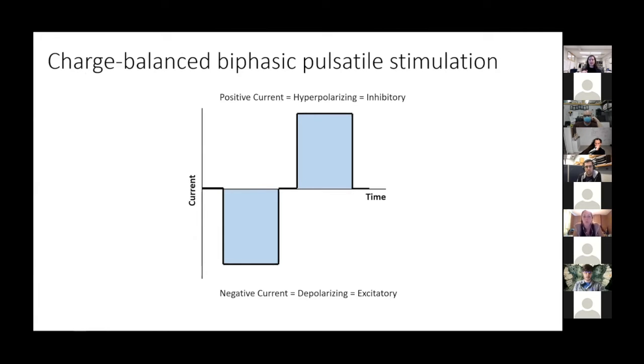Basically, you deliver a short excitatory pulse, and then you deliver an equal and opposite positive pulse to pull all the electrons back off your metal electrode, so that if you deliver a bunch of these pulses over time, you have no net charge accumulation on your electrode in the tissue, and you can avoid byproducts. While this is a really useful stimulation waveform, it's only really good to excite tissue. You can't directly use it to inhibit because you always have to deliver an excitatory pulse. That's where DC stimulation comes into play.